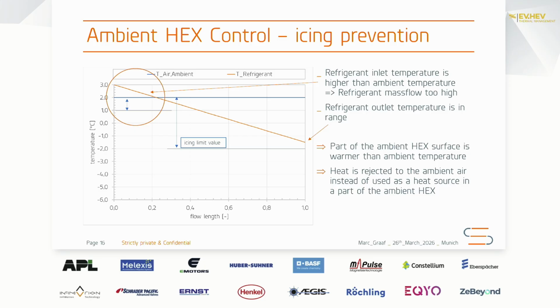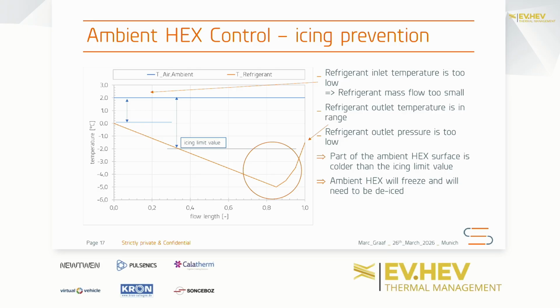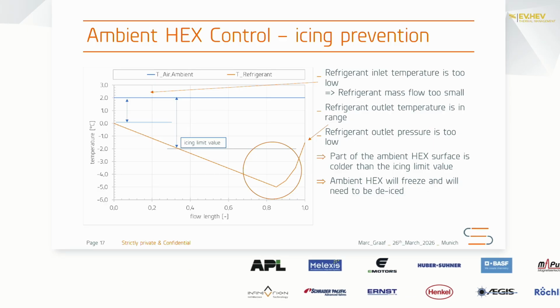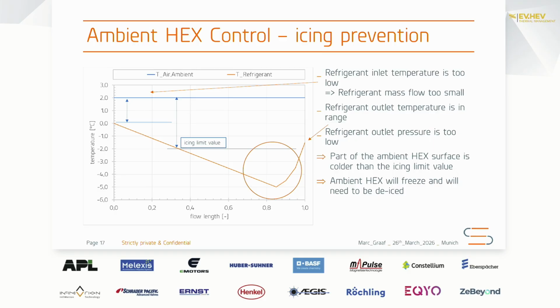So if you have a high pressure drop, that could lead to a temperature in a certain area of your heat exchanger that is higher than ambient temperature. So first you waste heat to the ambient, and then you have a smaller surface left to pick up heat, which is of course very inefficient. So it's necessary to control it in a way that this temperature is always below ambient. On the other side, if you have a control that is causing too much superheat, you are measuring your temperature on the outlet of the heat exchanger and think everything is fine. You can also have a pressure or temperature sensing on the inlet that you control, and also here you are fine, but because of the superheating, you have a lower saturation temperature on a part of the heat exchanger, and in this area that is below, let's say, that 5 Kelvin gap, for example, your heat exchanger would ice up, and this will grow over time on the total heat exchanger surface because you reduce the heat that you can pick up.